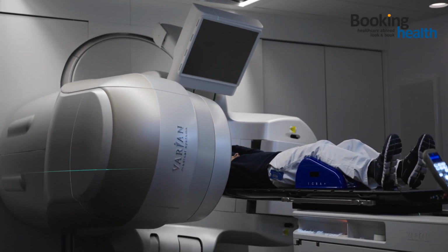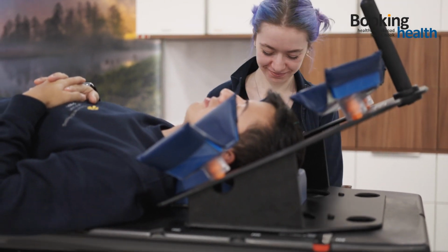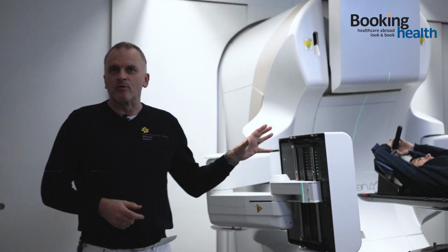If the tumor is in the wrong position, the patient can be positioned as required by the irradiation procedure, or the beams can be directed to the target area so that the irradiation proceeds according to the planned scheme. This can also be done through various mechanisms. For example, a tumor is marked with special gold pins.